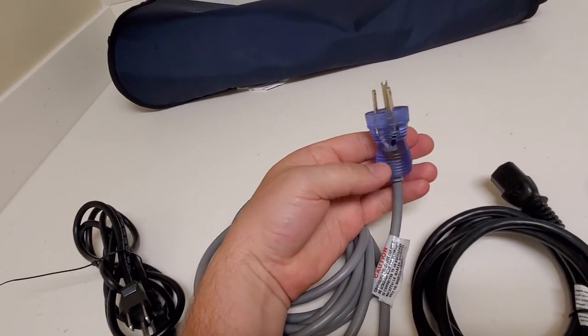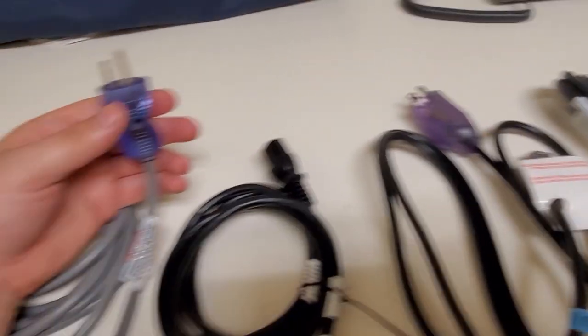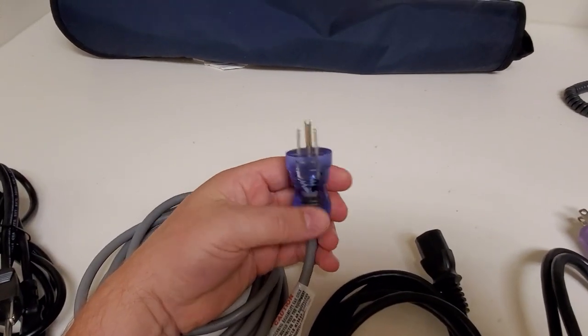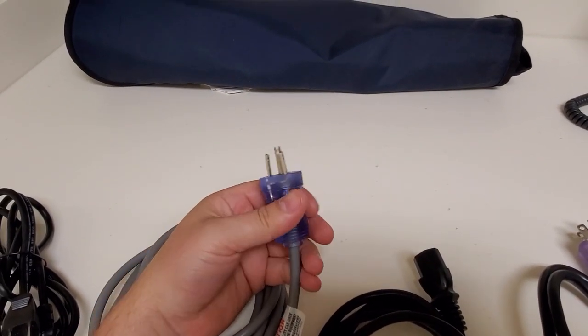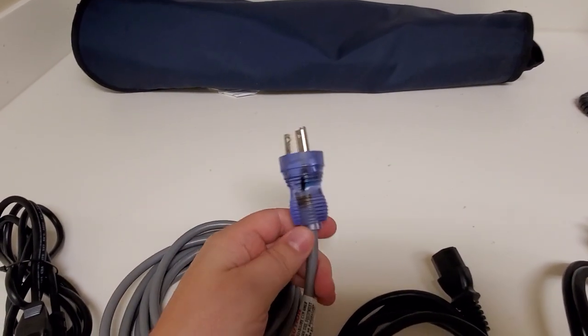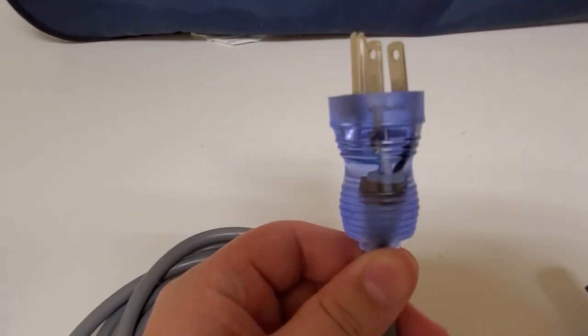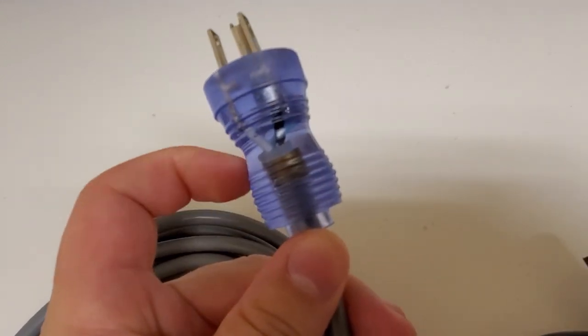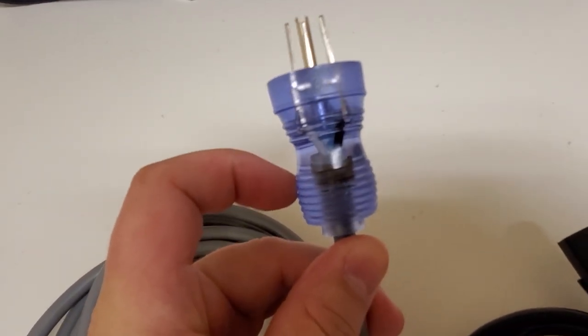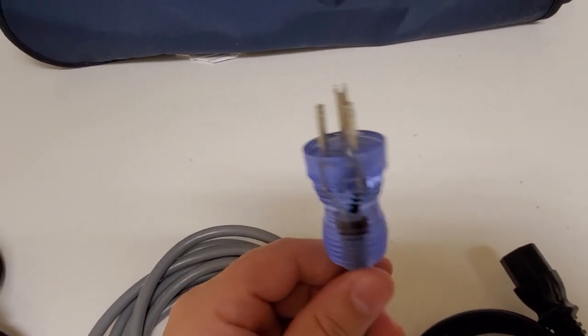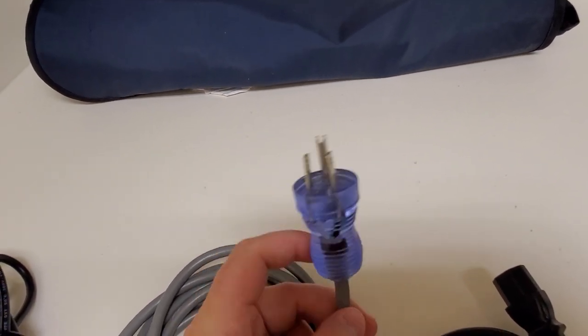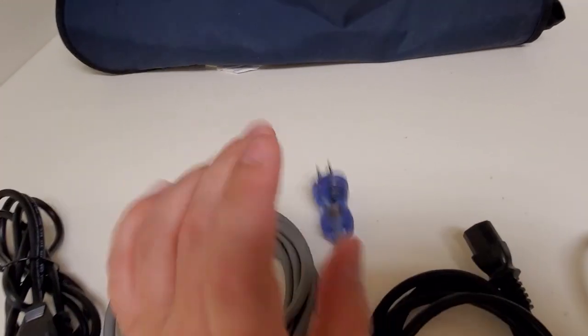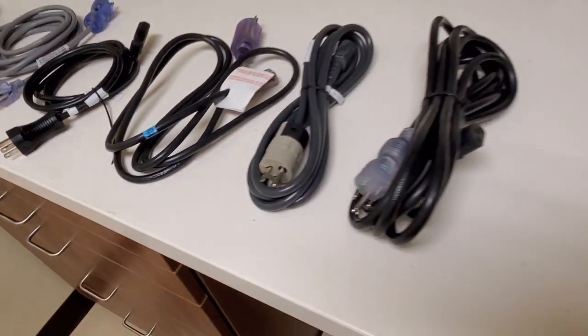So you can see that there's an indent in the plugs. You can see these ones here all have kind of the same thing. It's a larger diameter plug. It places your hand further away from the pins, as you can see. And there's an indent, usually, so that you can get a good grab on it when you're plugging and unplugging. There's something else I want you guys to take a look at. If you see right down in there, right around the outer sheathing inside the molded plug, there is a brass ferrule that's crimped around it. And what that adds is extra strain and yank relief so it doesn't pull this outer sheathing away from the inner cords, which still happens, unfortunately. So that's the basics of hospital grade plugs.